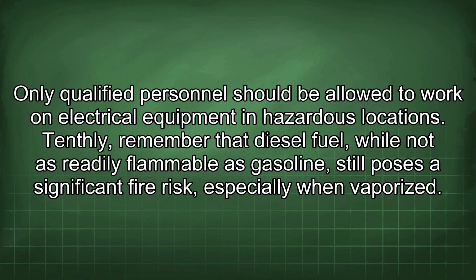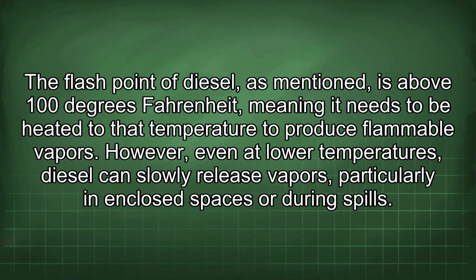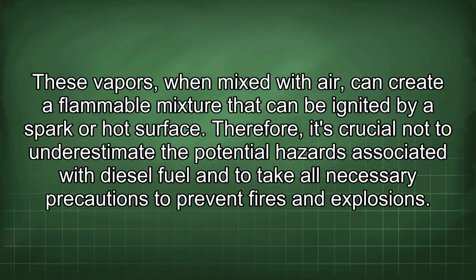Tenthly, remember that diesel fuel, while not as readily flammable as gasoline, still poses a significant fire risk, especially when vaporized. The flash point of diesel, as mentioned, is above 100 degrees Fahrenheit, meaning it needs to be heated to that temperature to produce flammable vapors. However, even at low temperatures, diesel can slowly release vapors, particularly in enclosed spaces or during spills. These vapors, when mixed with air, can create a flammable mixture that can be ignited by a spark or hot surface. Therefore, it's crucial not to underestimate the potential hazards associated with diesel fuel and to take all necessary precautions to prevent fires and explosions.